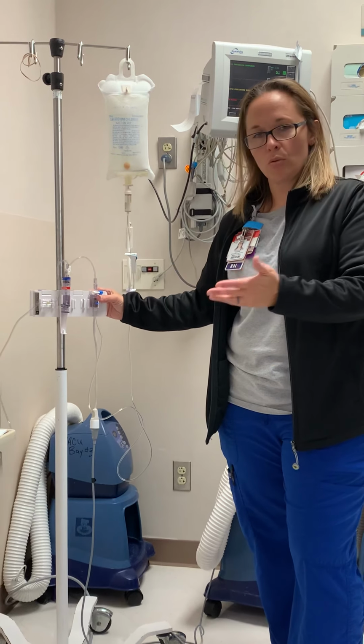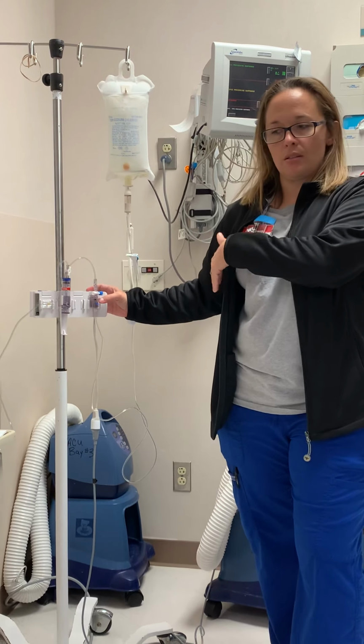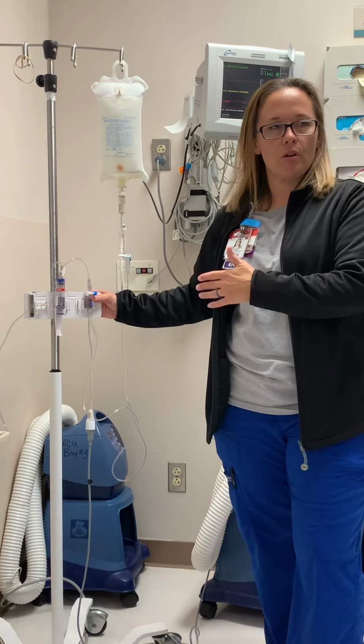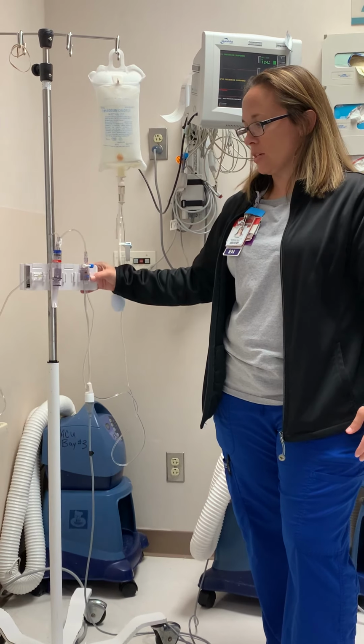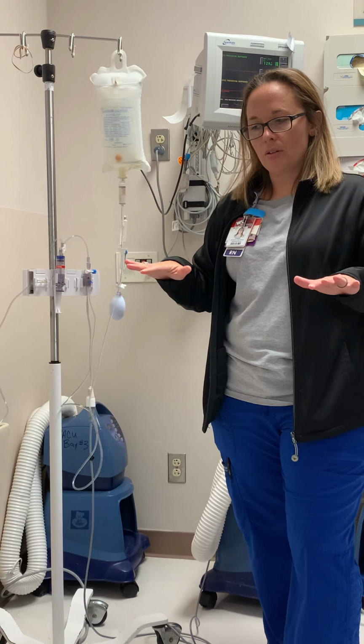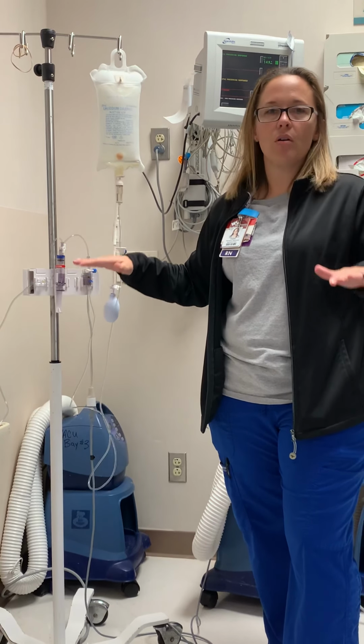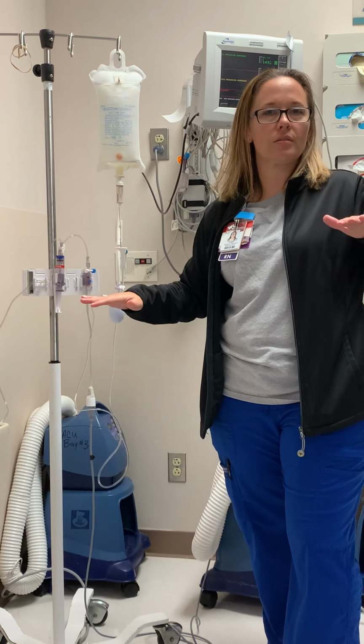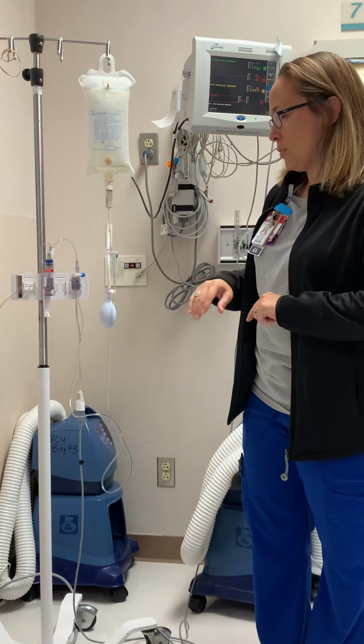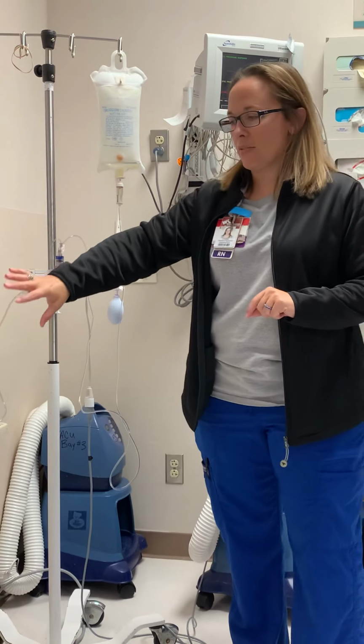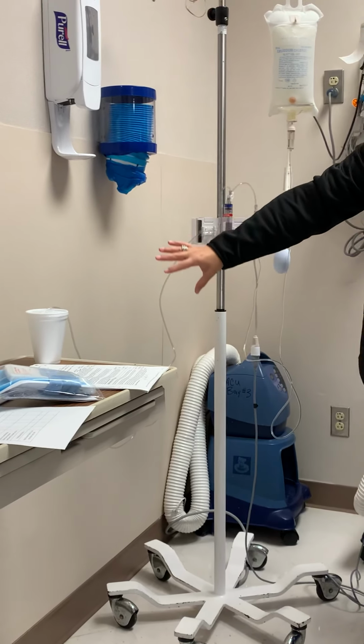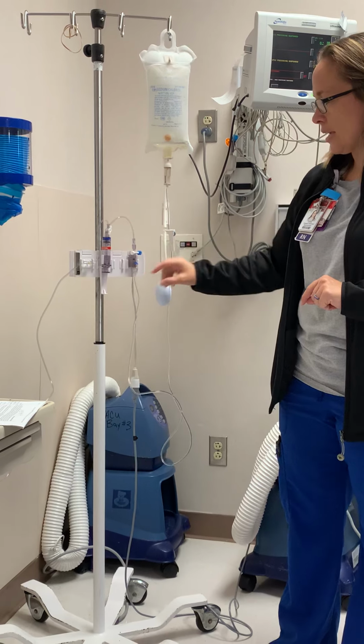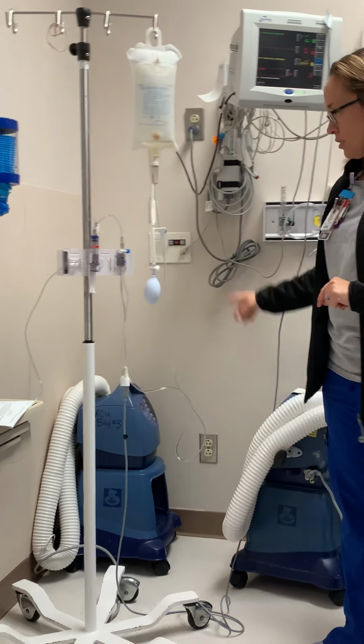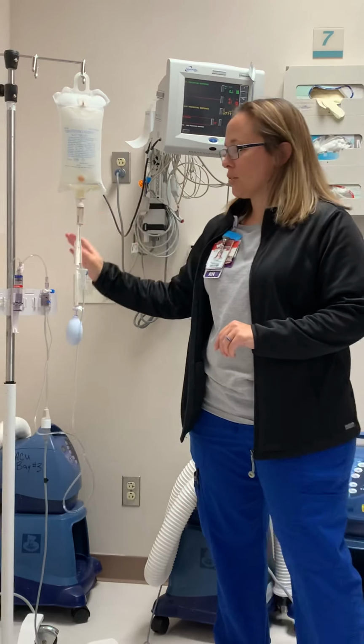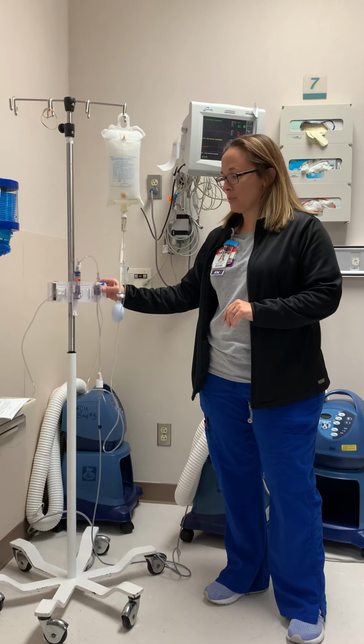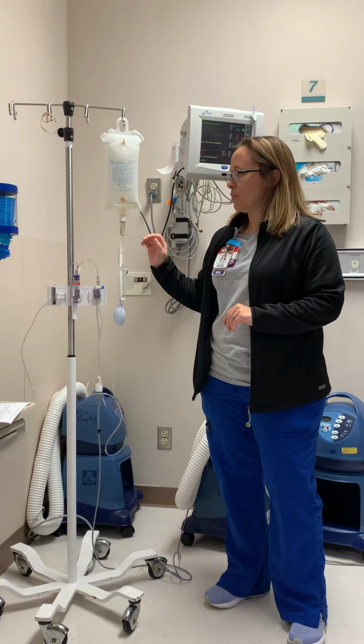Now there's another option, of course, to lay this in the bed and have it at an intercostal space, but typically we put it on a pole, or it comes out on a pole, and we adjust it as needed, because it's important for the leveling of the transducer to be level with the heart. That way we're not having an atmospheric pressure difference. We can go over that a little bit more in a second. Essentially, you want to have this in line. So we're assuming our patient's over here, and you want to have the flow going easily so it's easily traced to the monitor.